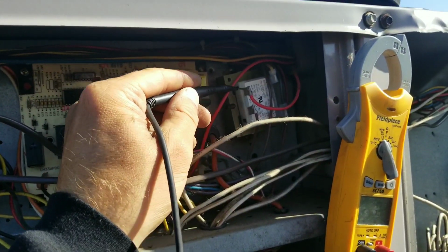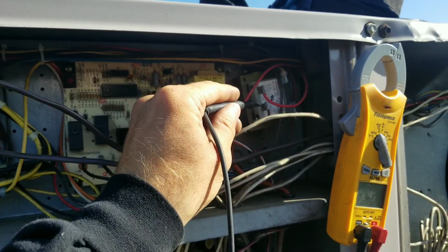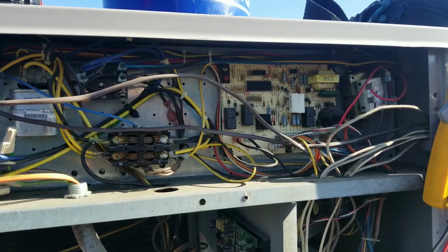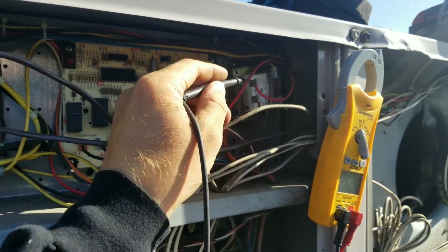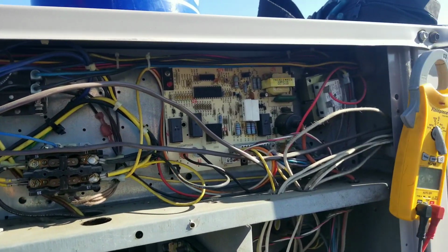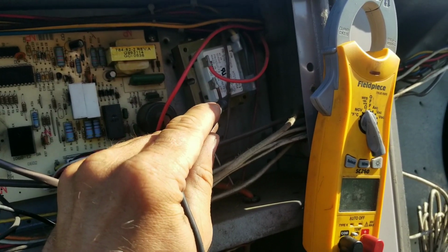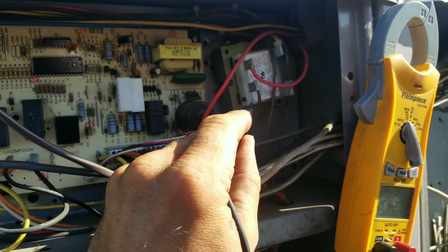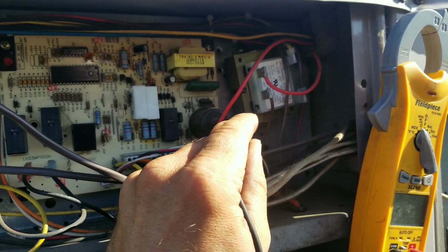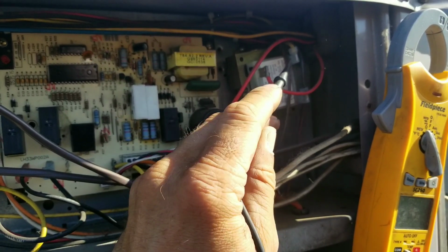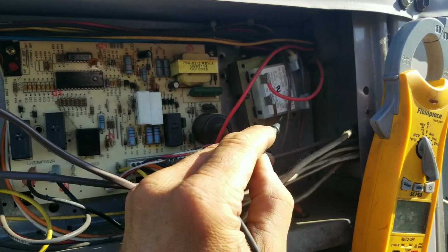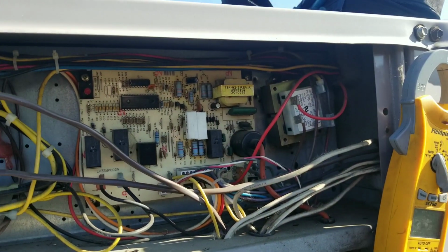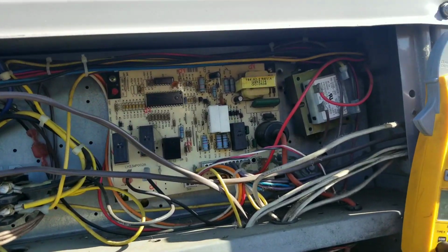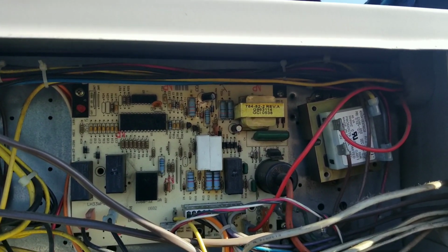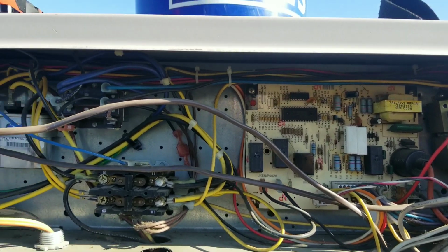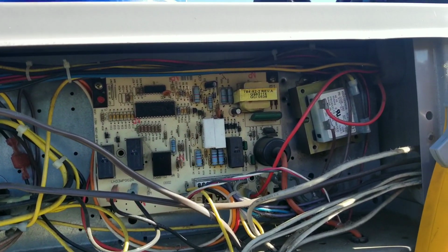Now, if you notice, our low voltage side all have continuity to ground. Now, that still is somewhat confusing for me, but I was always told the reason why our 24 volt will always have continuous ground, or will always be grounded, is just for safety. For example, on this transformer right here, we have 460 on our primary side and 24 volts on our secondary side. And from what I understood from the old guy who taught me, is that we ground it for safety, just in case this shorts out, or just in case we have a direct short from our primary to our secondary, then our ground will be right there and it'll trip our breaker before anybody gets hurt. Again, I'm not an electrician. I have looked into that subject a little bit, and really everything always goes back to safety for the most part that I've found. But if anybody out there knows a little bit more than I do, let me know. Put it in the comments.